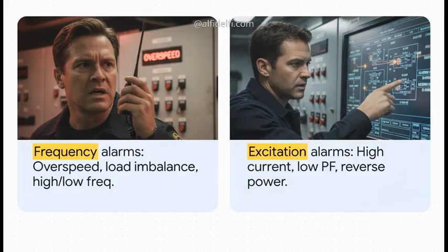But for excitation loss, your alarms are a completely different beast. High current, low power factor, reverse power, and the LOE relay. Your immediate response here is all about identification. You have to ask yourself which paralleled unit is actually the faulty one. You still need to quickly inform the bridge, of course, but the urgency shifts a bit because, remember, you have a healthy partner already online to lean on.